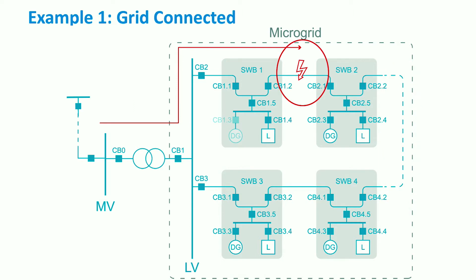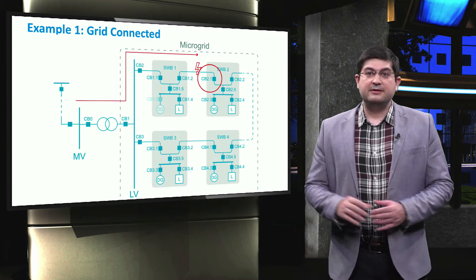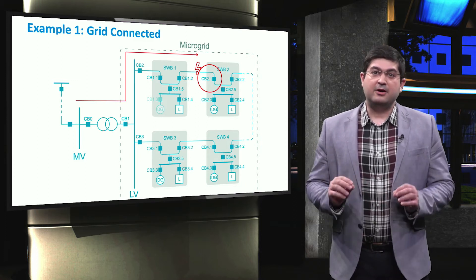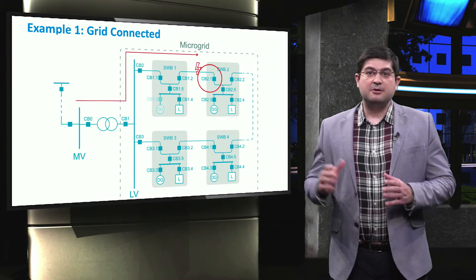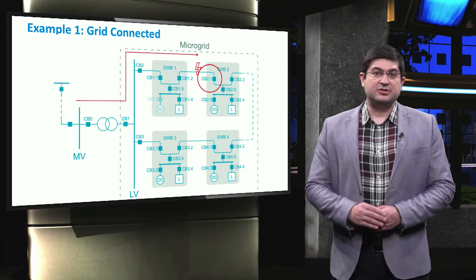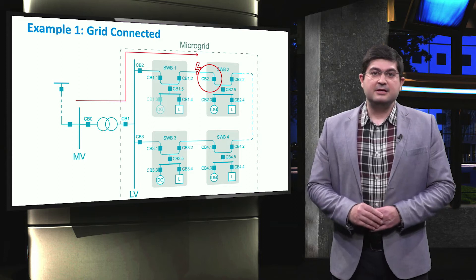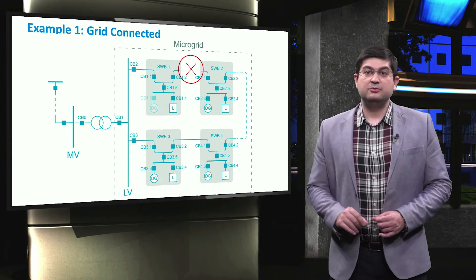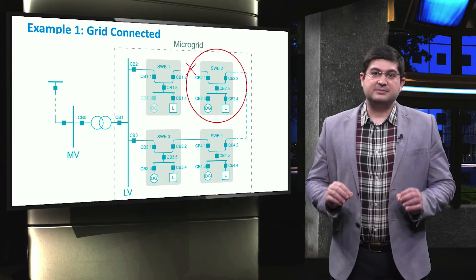If a fault occurs between switchboard 1 and switchboard 2, then the fault current is supplied from the grid. For this case, the fault current will pass through circuit breaker 1.2. Then circuit breaker 2.1 will be opened using a follow-me function of CB 1.2. This function helps disconnect both the head and the end of each line as soon as one of the two relays detects the fault. Once these two circuit breakers 1.2 and 2.1 are opened, switchboard 2 becomes disconnected from the grid.